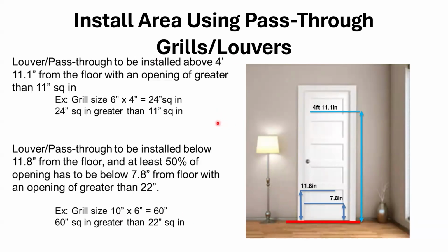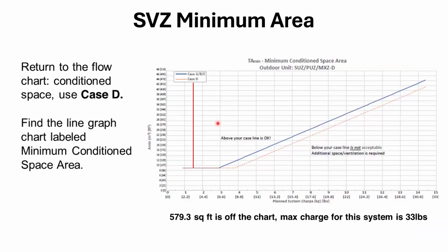So if we do that, it changes our square footage right down here. Since we did all that and added the transfer grills, we're allowed 579 on the square footage. Here's our square footage right here, and then we're on case D. So you have to go back to this chart and use the case D line. When you do that, which is this line, you'll find out if it's off the chart, meaning we can't have a system that has more than 33 pounds of refrigerant.